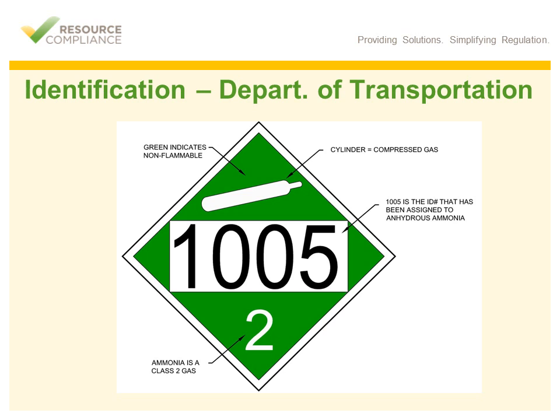There are several labels and placards used to identify containers and pipes that contain ammonia. The first system we will discuss is the DOT placard system. Whenever a trailer or rail car is carrying ammonia, it should be placarded on all four sides with the label on this slide. Each DOT placard has four required components: an ID number, class number, background color, and a symbol. For ammonia, the ID number is 1005, the class number is 2 indicating a compressed gas, the background color is green indicating that ammonia is generally considered non-flammable, and the symbol is a compressed gas cylinder, which provides a warning of high pressure within the container.